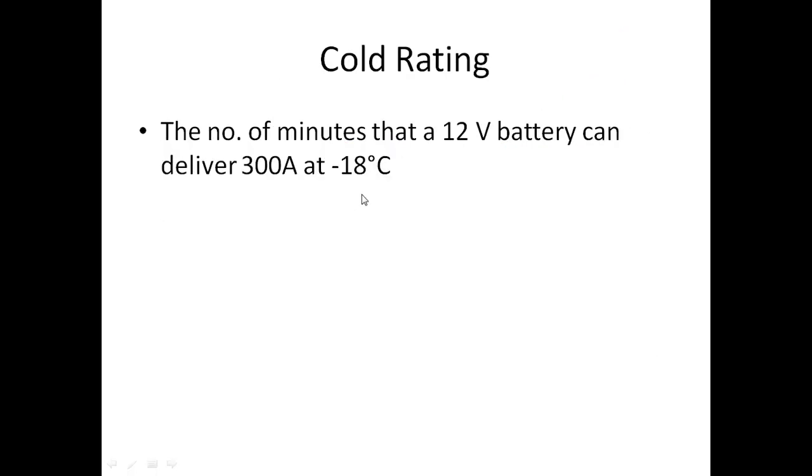Next is the cold rating. It is also related to car ignitions and other uses, suppose we are using batteries for starting the generators in cold environment. So the cold rating is the number of minutes that a 12-volt battery, these ratings are given for 12-volt batteries, can deliver 300 ampere at minus 18 degrees centigrade.